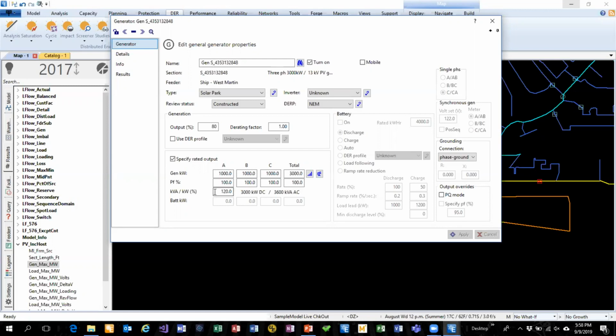I could also go the other way and set this thing to like 0.5 -- sorry, it's a percent, 50%. So at 50%, I've got 3 megawatts DC, 1.5 AC. That means as the sun comes up, this thing is going to ramp up, and then it's going to clip off, giving a flat profile, then drop back down. Consumers like that a lot, and I think utilities do too, because you have a consistent output throughout the day. We know the DC panels could do more, but our inverter is clipping that.